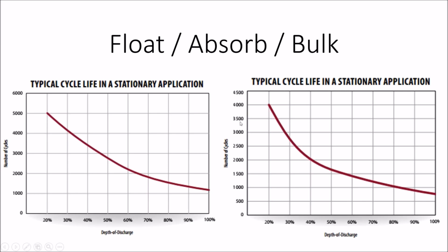Now, it has to be taken with a grain of salt because these charts do not reflect how the battery is being used in the field. You'll often get discharge rates for lead acid, saying this is what it can provide at 20 hours of constant use, this is what it can provide at 5 hours of constant use, and it has to do with how quickly the battery is being discharged. There's also impacts of temperature. Now, I like putting my batteries in a temperature regulated environment, but you can't always do that.